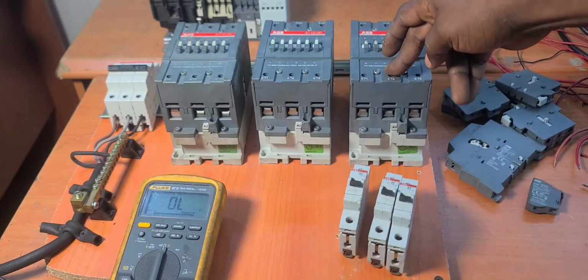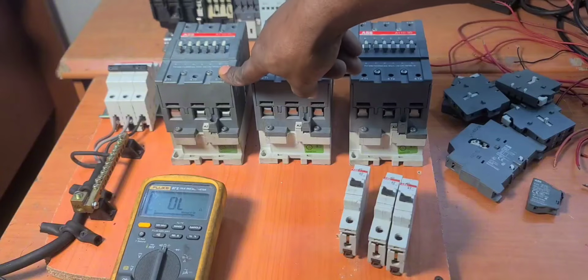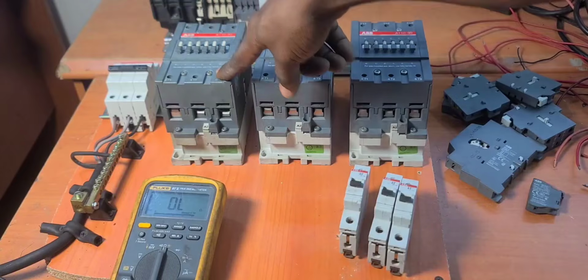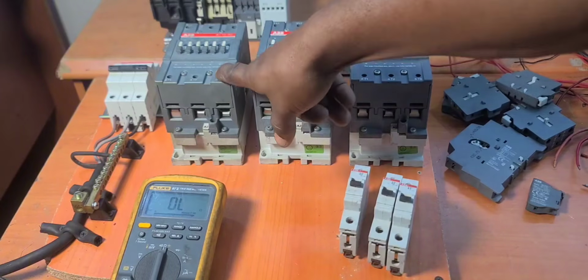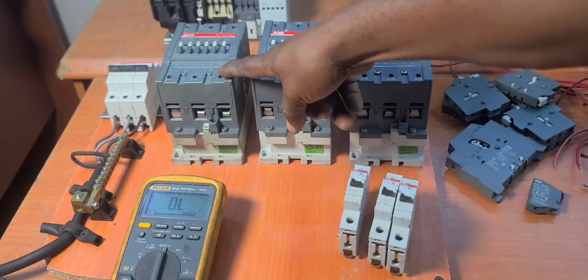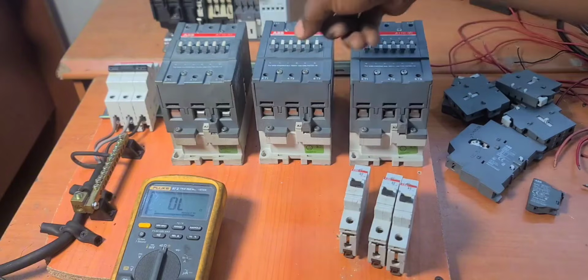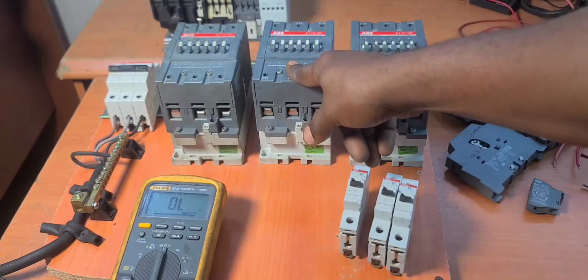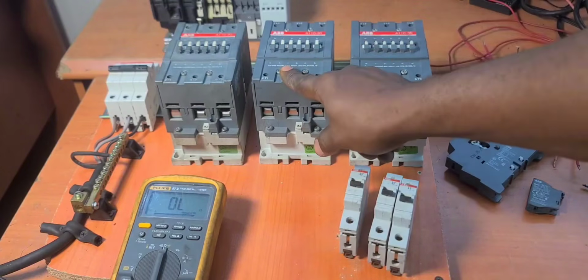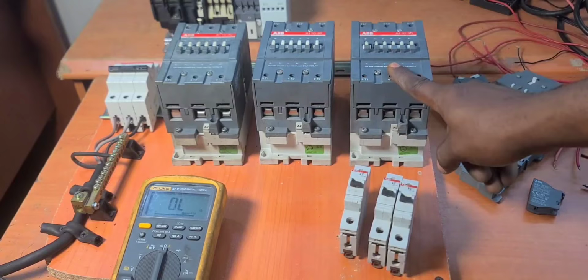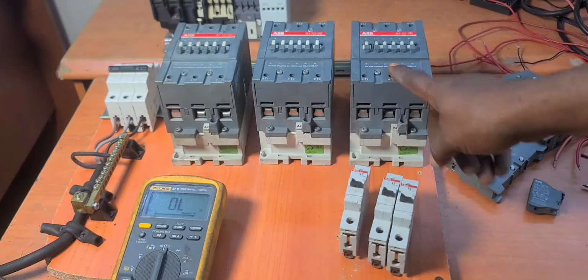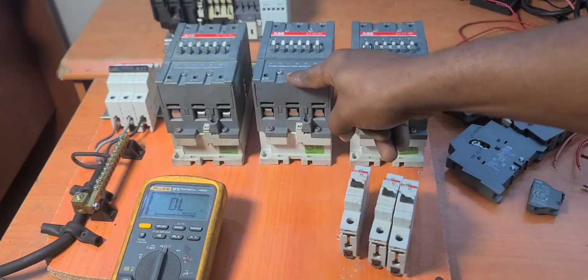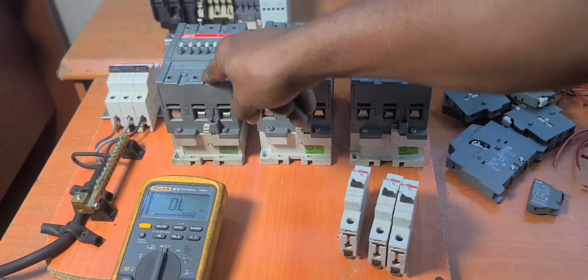So the configuration would be that solar is the priority. That is, the main source of power is solar. So when solar fails, when solar goes out, say in the evening, and when the sun sets, we don't have solar at that time, mains should take over. Mains will continue, and then if mains fails, generator should take over. And if there is mains and there is solar, mains should be off while solar should continue.